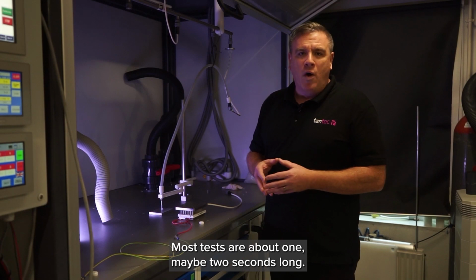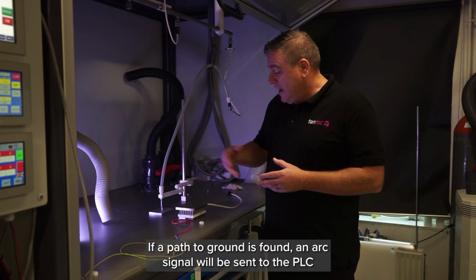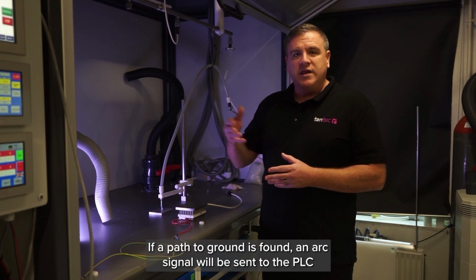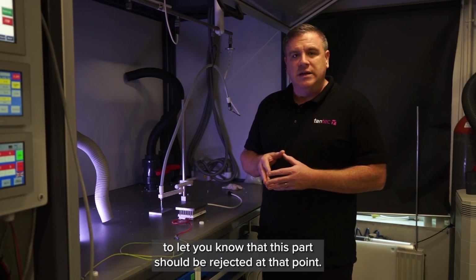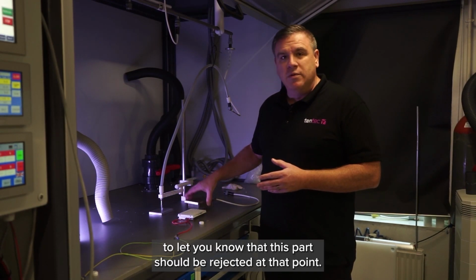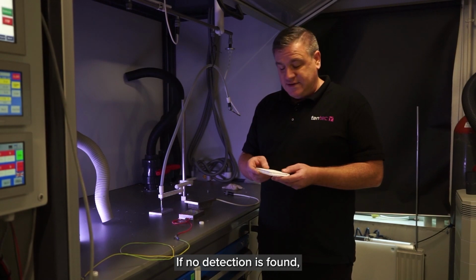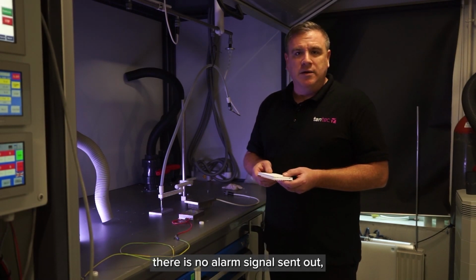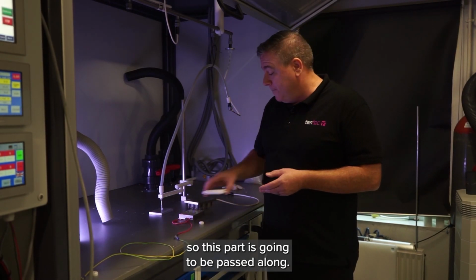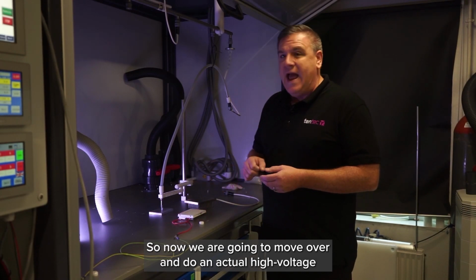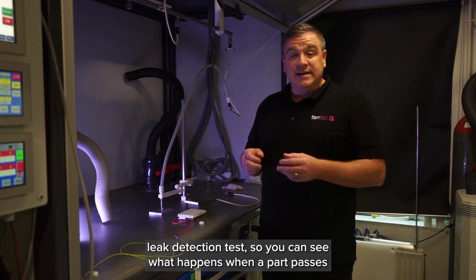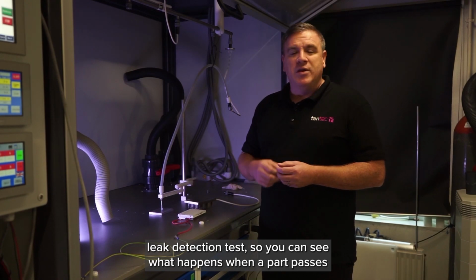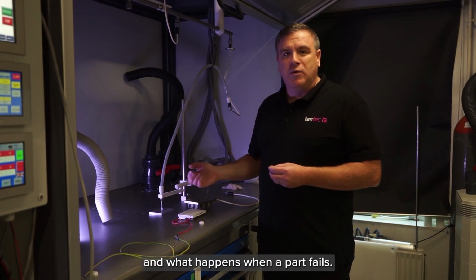Most tests are about 1, maybe 2 seconds long. If a path to ground is found, we'll then send an arc signal out to the PLC to let you know that this part should be rejected at that point. If no detection is found, there is no alarm signal sent out, so this part can then be passed along. So now we're going to move over and do an actual high voltage leak detection test so you can see what happens when a part passes and what happens when a part fails.